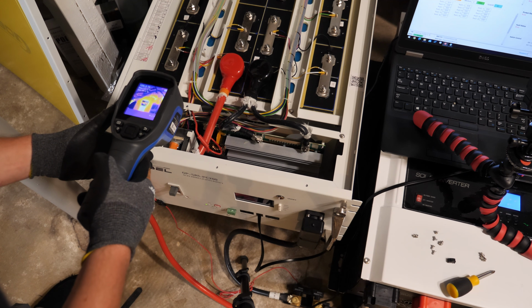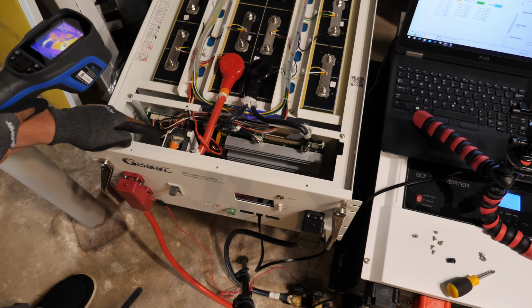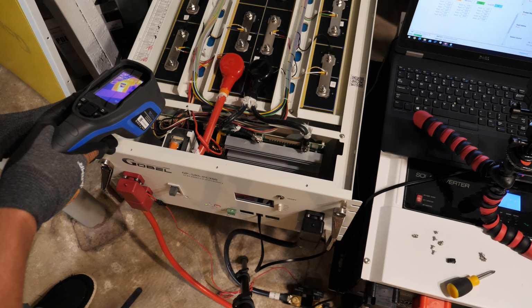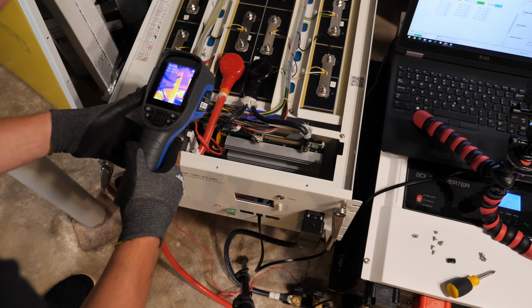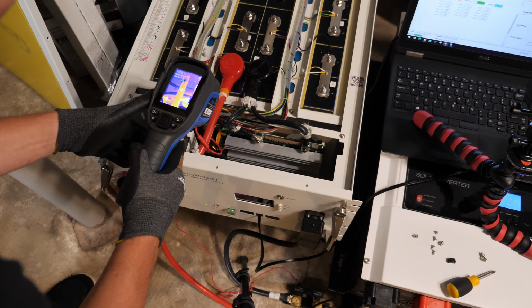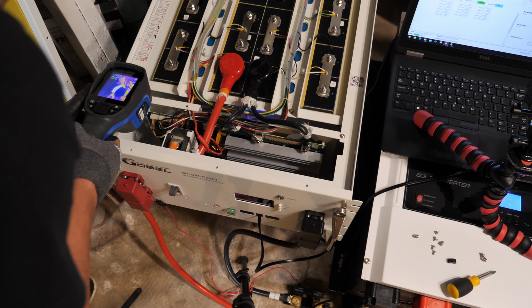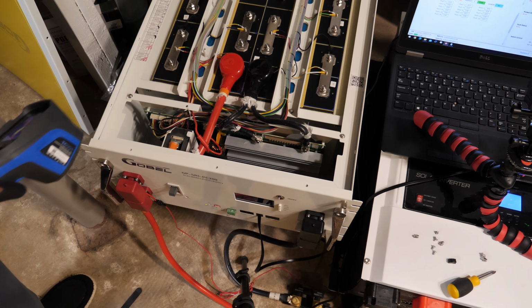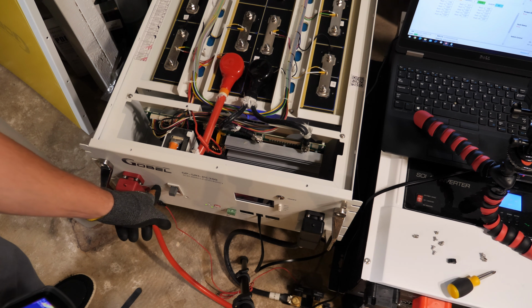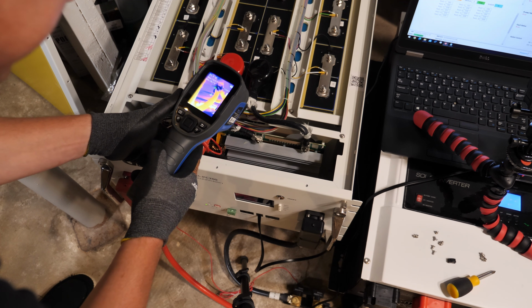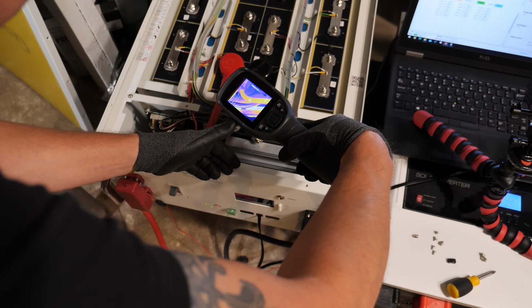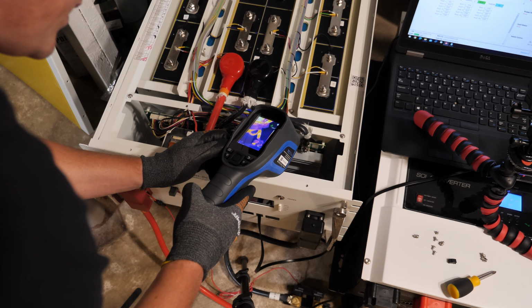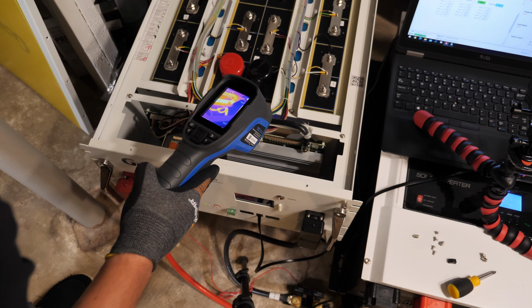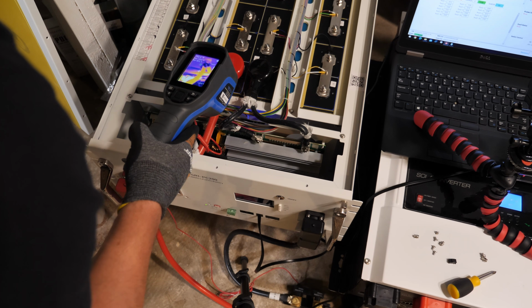Over here at the circuit breaker, the terminal is around 118 degrees Fahrenheit. The battery cables, this one is 103 degrees Fahrenheit. The ones down here on the front are around 110, just behind the terminals, that's the positive. The two small ones are 103.6, and that's 112 on the negative side. I'd say everything's looking pretty good in here, not too hot.